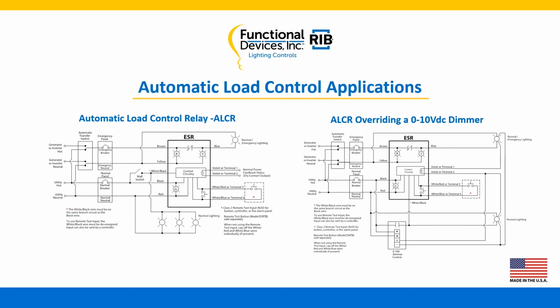The section right below that is where it talks about white, red, and white, blue wires. That's your remote test wires. So our remote test is sitting there. You're able to do that. Many states, many counties within the states require that test button out there for the inspector to come through and test periodically. It could be 6 months, it could be yearly. So we have to provide that. That is what code says. So that's how we do it.